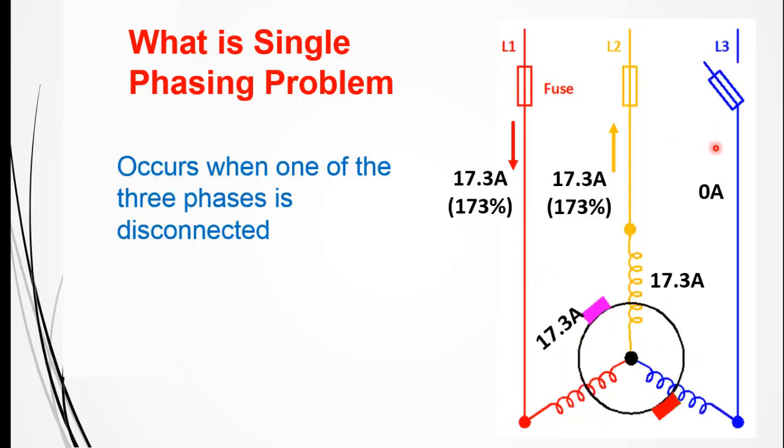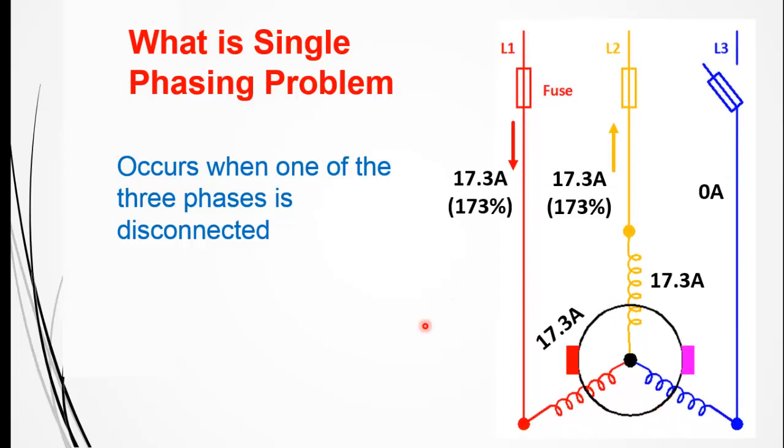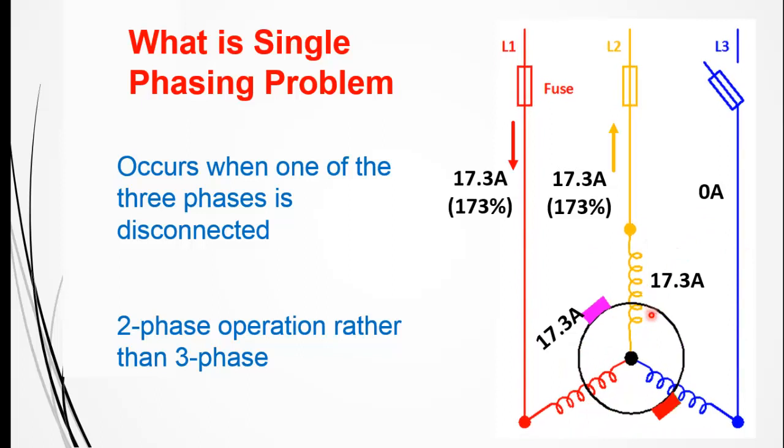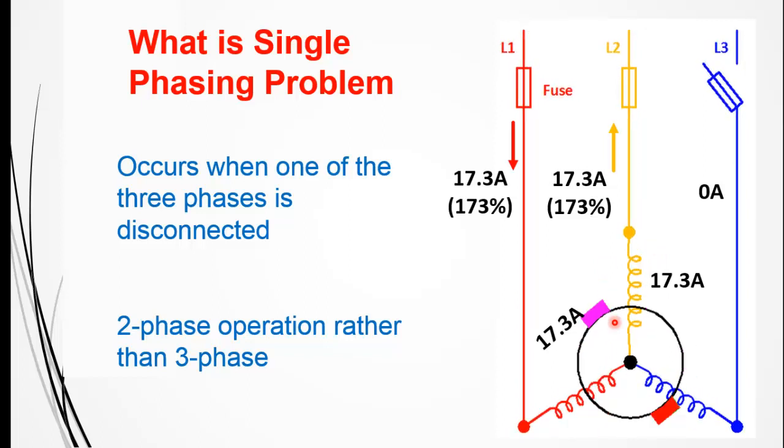It occurs when one of three phases on the motor gets disconnected or fails. This single phasing problem is the worst scenario of voltage unbalance on a three-phase motor because the motor now continuously runs on two phases instead of three. As you can see here, there is vibration and noise that appears in the motor, and I will discuss the reason why this happens later in the video.